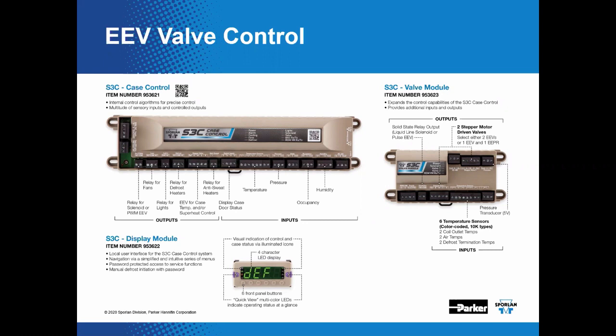No, me either. We offer a complete online training class that covers this particular control. This case controller drives the EEV, the EEPR, and/or liquid line solenoid valves, and it also has onboard relays to control the lights, defrost cycle, fans, and anti-sweat heaters. We're using this as an example for all of the schematics that we're going to show as this proceeds. The Sporlan S3C case control product line includes the case controller, a display module so you can see what's going on, and a valve module, and that all support open protocol communications via things like BACnet and Modbus.